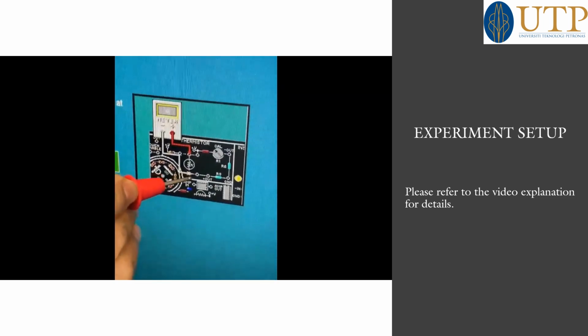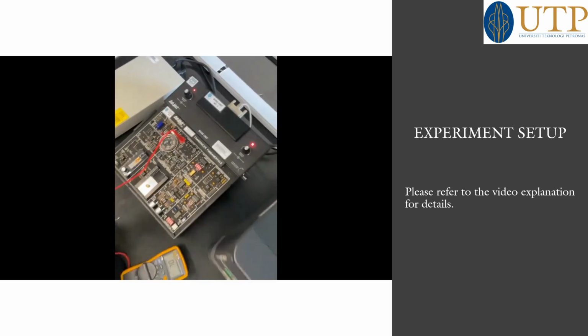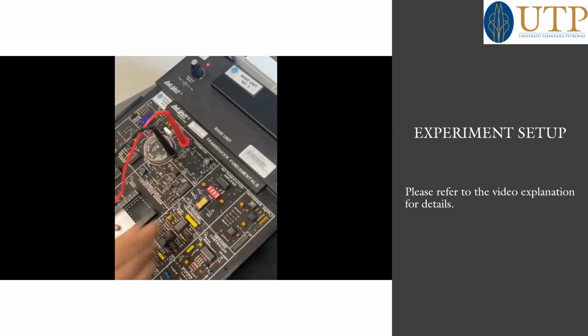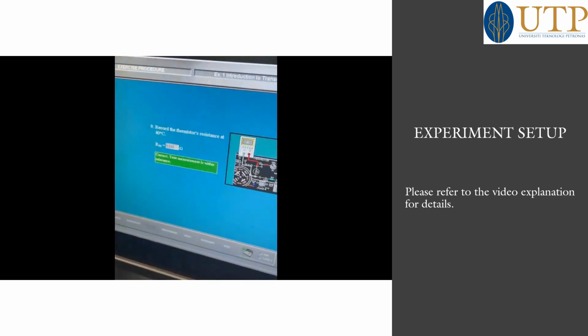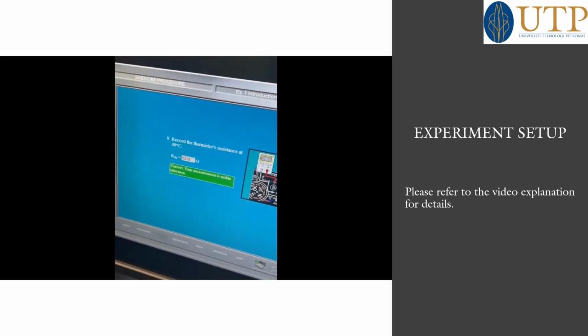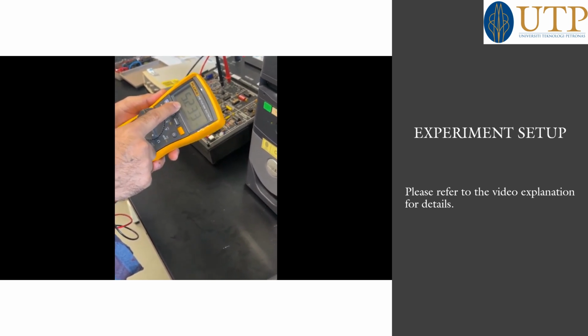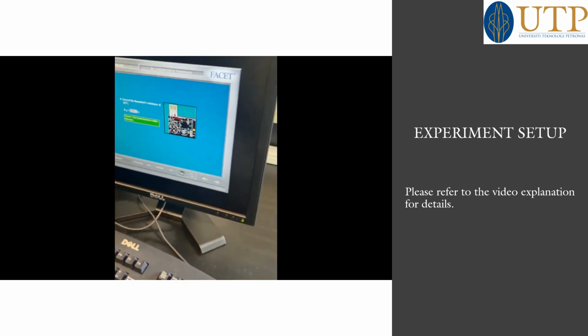Now record the thermistor resistance. We fix the red lead here in the thermistor, and the second one should be here. Now we are fixing them properly. Record the thermistor resistance as you fix the negative and positive of the multimeter. You will find the ohm meter reading, meaning resistance, here: 5.20 something. When you put in these values, you will get the result. Proceed.